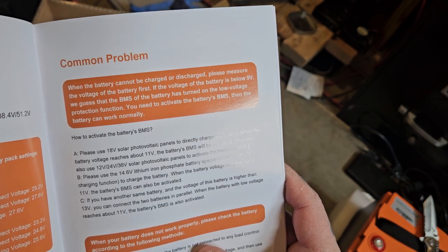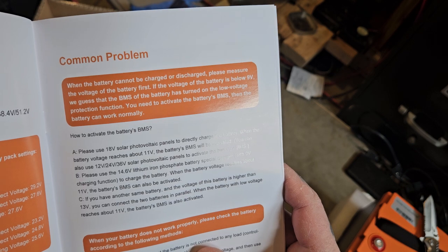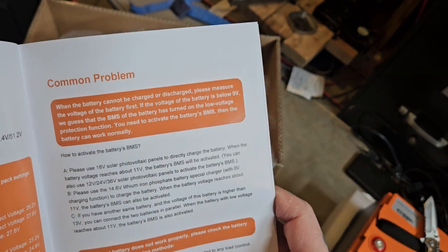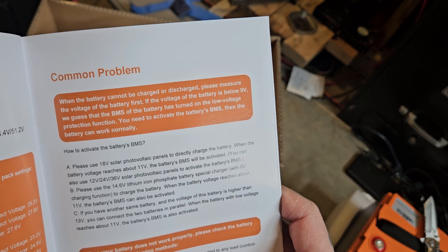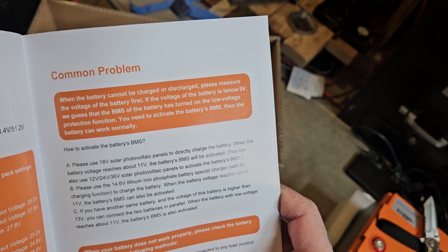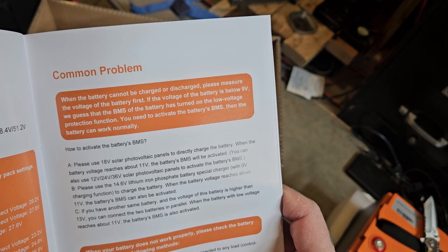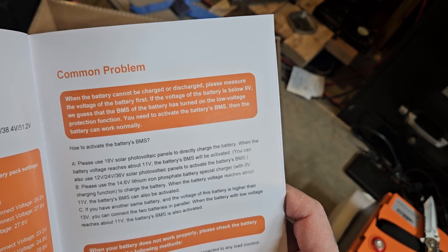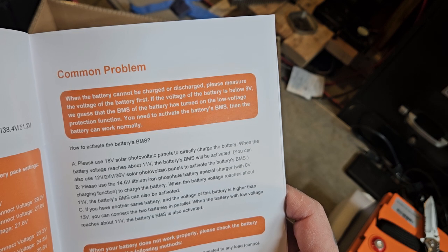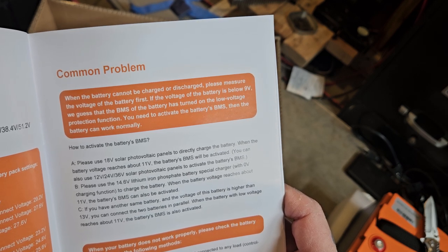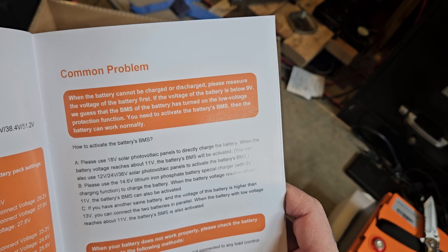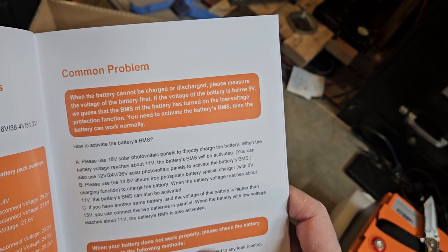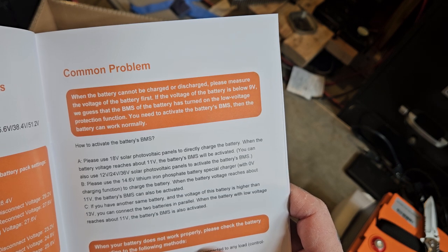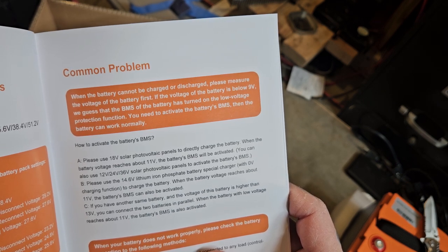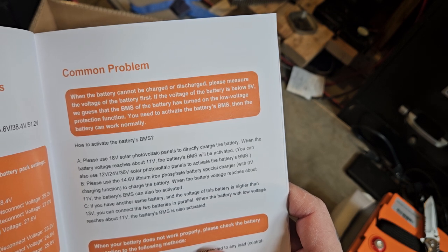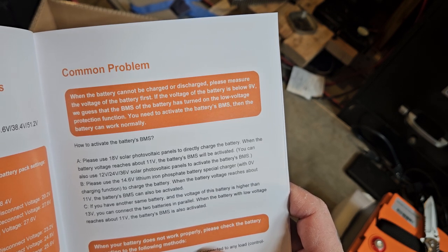Please use 18 volt solar power to directly charge the batteries. This is quite strange. When the battery cannot be charged or discharged, please measure the voltage of the battery first. If the battery voltage is below 9 volts, we guess the BMS has turned on the low voltage protection function. You need to activate the battery's BMS so it can work normally. How to activate it: use 18 volt solar photovoltaic cells to directly charge the battery. When the battery voltage reaches about 11 volts, the BMS will activate. You can also use 12, 24, and 36 volt photovoltaic panels to activate the battery's BMS.